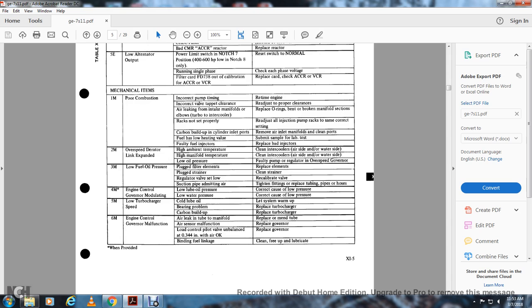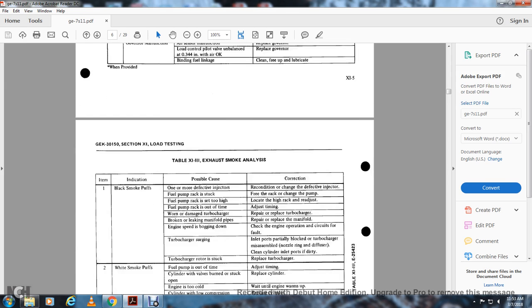Item 5M, low turbocharger speed. Possible causes: cold lube oil, let system warm up. Bearing problem: replace turbocharger. Carbon buildup: replace turbocharger. Item 6M, engine control governor malfunction. Problem and possible causes: air leak in the manifold, replace the tube. Air sensor malfunction: replace governor. Load control pilot valve unbalanced to 0.344 inches with air: replace governor. Binding fuel linkage: clean, free and lubricate.